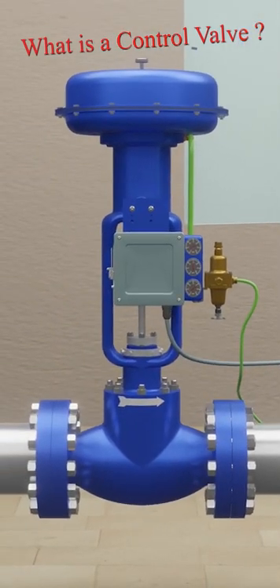Because the PLC signal is electrical, most common signal type is 4 to 20 milliampere. The control valve may require a device to convert that electrical signal into a pneumatic force so that it can operate.